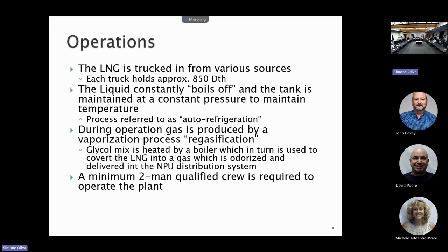This is done through those 3 new cascading boilers, just under 1 million BTUs each. If you're familiar with the industry, there's a tag for 999,999 BTUs that goes on each one of those levels. If you've bought a boiler for your own house, it's usually rated 199,900 — there are reasons for that, insurance reasons and things like that. So they're very specific, but we have 3 of those.